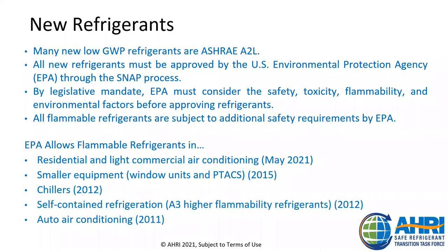Currently, the US EPA allows flammable refrigerants in residential and light commercial air conditioning as of May 2021, smaller equipment, window units and PTACs back in 2015, chillers starting as early as 2012, and self-contained refrigeration even had a SNAP listing of A3, higher flammability refrigerants, back in 2012, and auto air conditioning back in 2011. And some key points about the transition from the AIM Act.